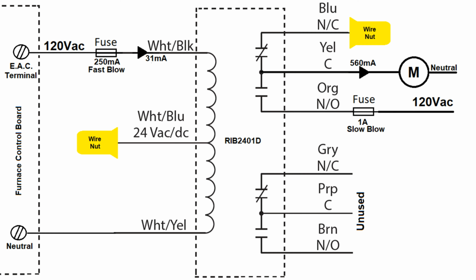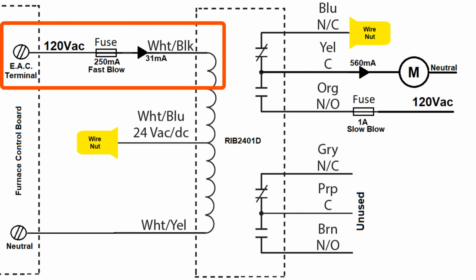One other commenter said he'd use a fuse to protect the electronic air cleaner output on the furnace control board. Now, that output is rated at 1 amp, and the relay coil is rated at 31 milliamps at 120 volts AC. 31 milliamps is 0.031 amps. So there's no risk of overloading this 1 amp EAC circuit with this relay. But the slim possibility of a short in the relay or circuit might justify using a fuse to protect that expensive furnace control board. So out of an abundance of caution, I added a 1/4 amp fast blow fuse to the EAC output signal.